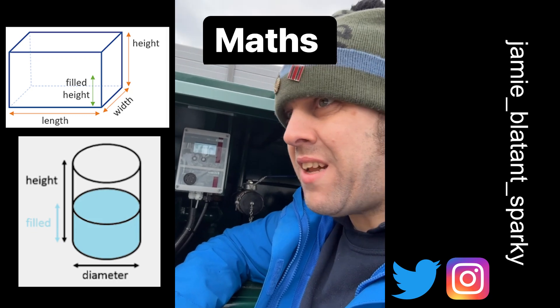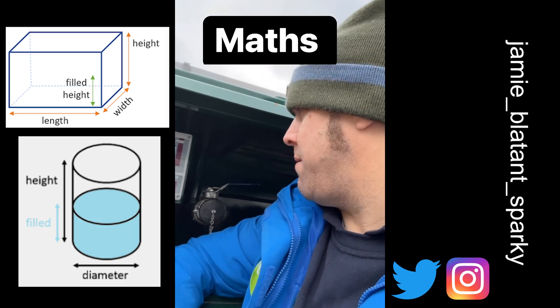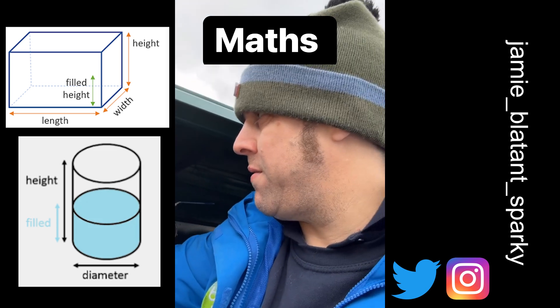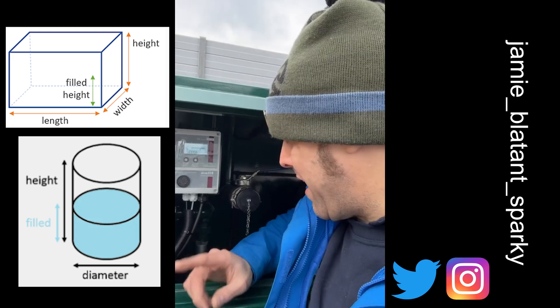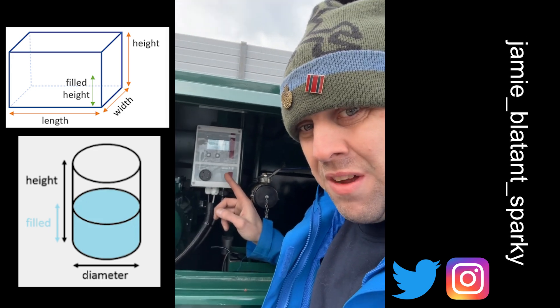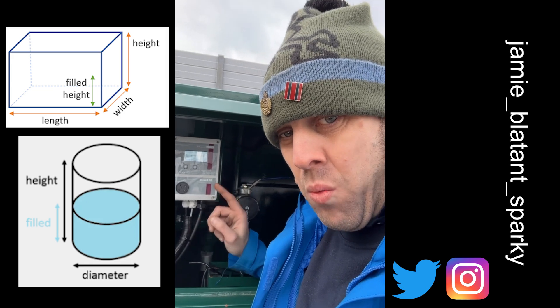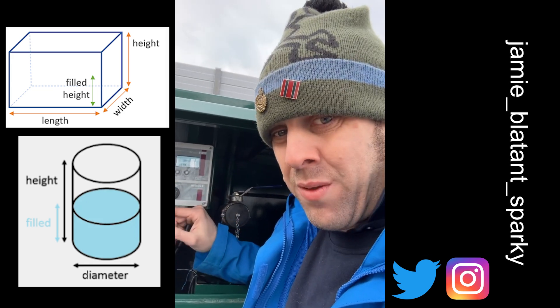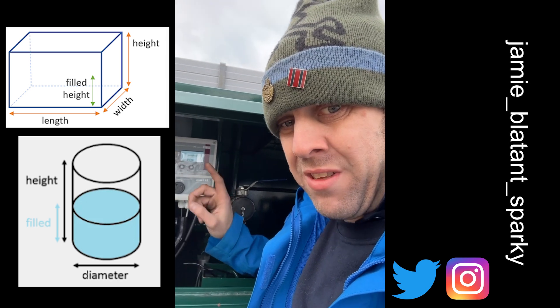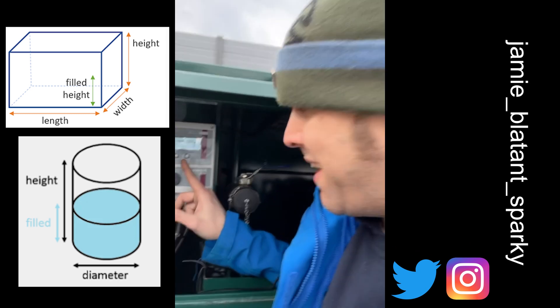Let's talk about maths. I want to calibrate this tank gauge. This tank gauge is capable of doing its own internal maths — you tell it how long, high, and wide the tank is and it tells you the value of the tank. When you drop in a pressure transducer it looks at that pressure, based on the values you put into it, and gives you a litre reading.